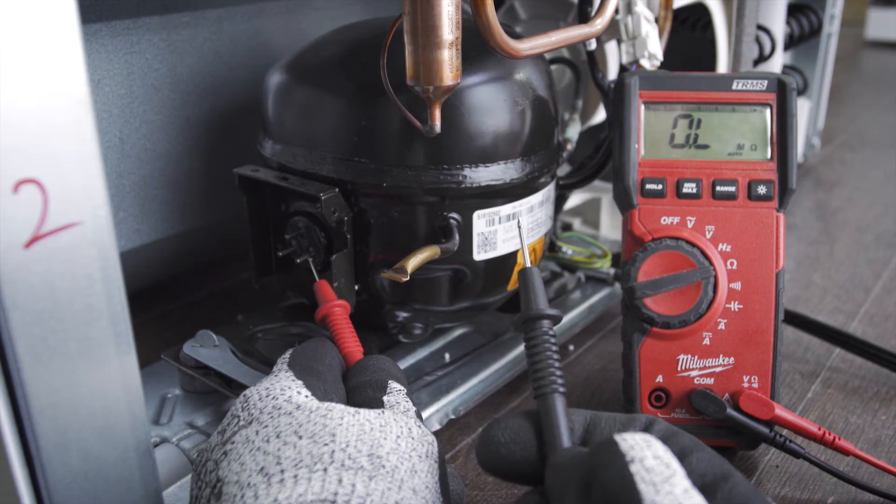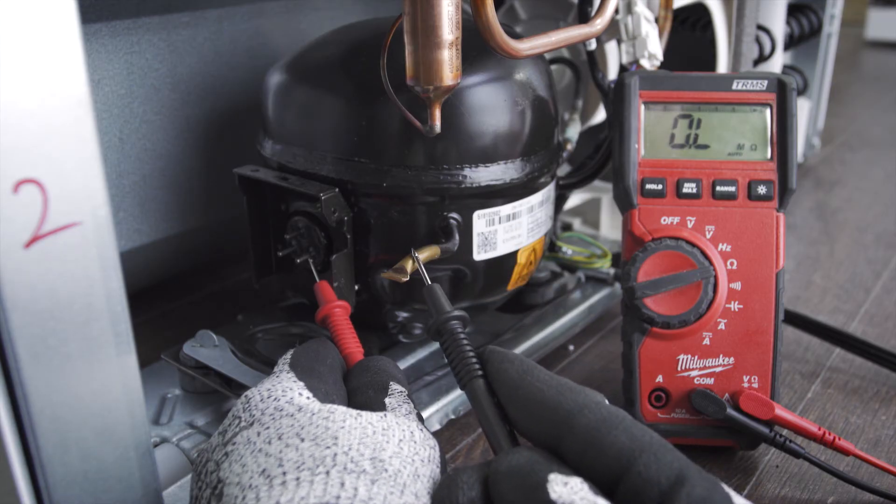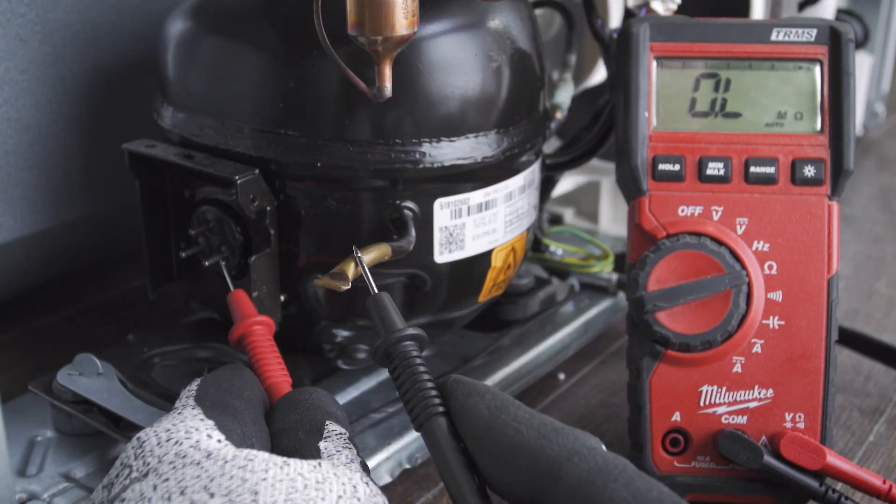You can also test the compressor for a short. Test between each terminal to any bare metal on the compressor. Keep in mind this won't work on a painted surface, so you'll likely have to find the ground wire or one of the copper pipes. If there is continuity then the windings are shorted to ground.